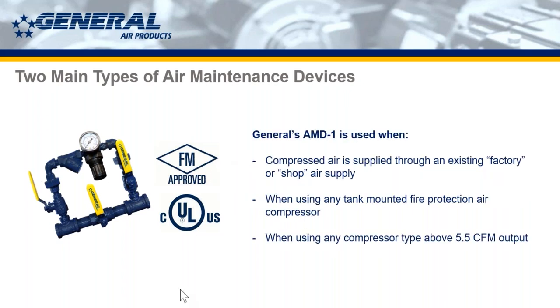So an AMD1, or an air maintenance device, is used when compressed air is supplied through an existing factory or shop air supply. So if you have an existing air supply in a facility and you're running a line from that to the sprinkler system, you're going to put an AMD1, or an air maintenance device, in line there to regulate that pressure. That was really the invention of the air maintenance device, going way back in the standard, as dry systems were starting in a lot of manufacturing facilities that already had large compressed air supplies.